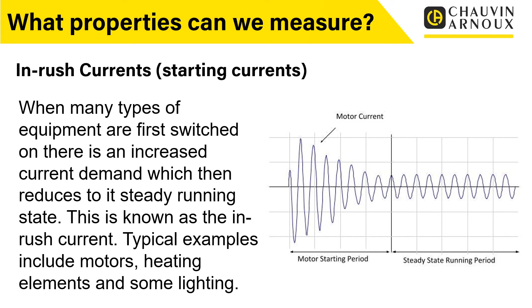So in power quality, sometimes we can set up the instruments to look particularly at these inrush currents to be able to quantify them, and then we can design the installation to allow for those characteristics, because it isn't a fault, it's a characteristic of that particular load. But we need to be aware and we need to design the installation to allow for that. And if that hasn't been done, sometimes this can be where you're chasing faults and finding what's gone on, and then you can alter and redesign circuits to operate correctly.